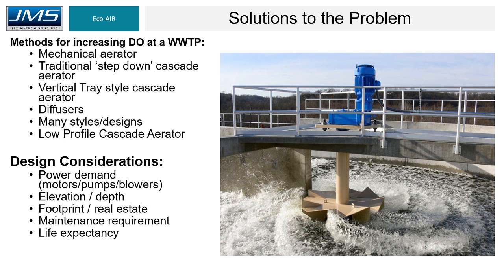Some solutions to the dissolved oxygen problem: several methods for increasing DO at wastewater treatment plants include mechanical aerators, traditional step-down cascade aerators, vertical tray style cascade aerators, diffusers, and the low profile cascade aerator. When selecting equipment, design considerations should include power demand, available elevation or depth, footprint or real estate, maintenance requirements, and desired life expectancy.